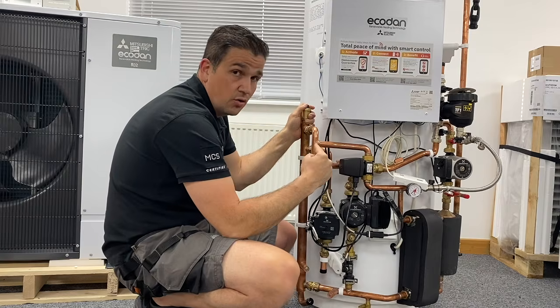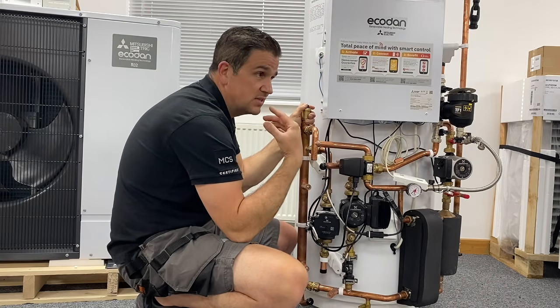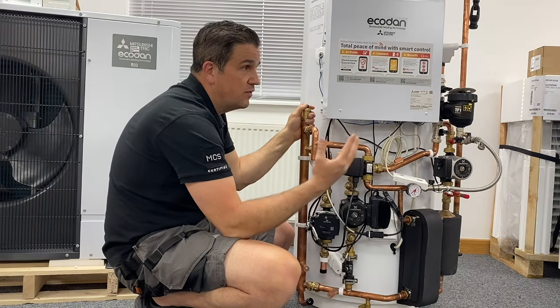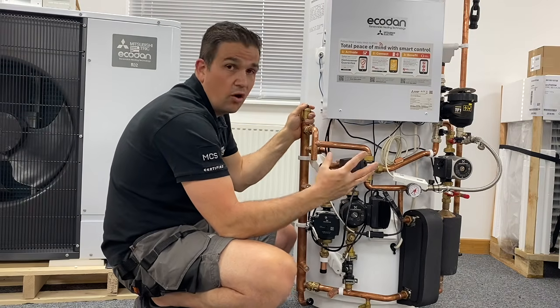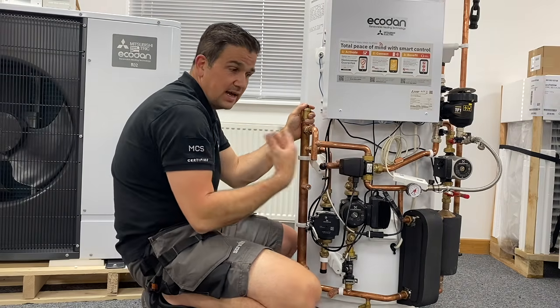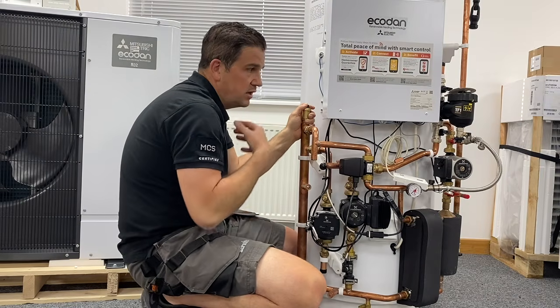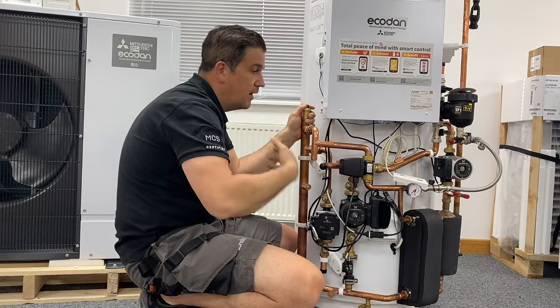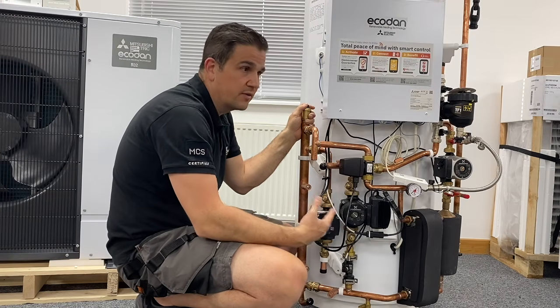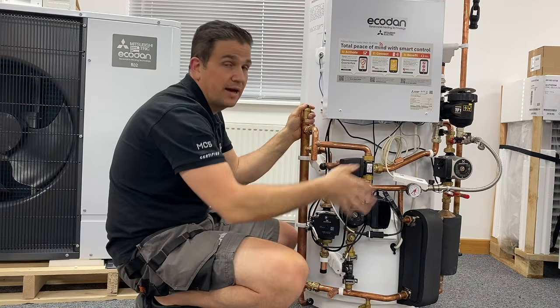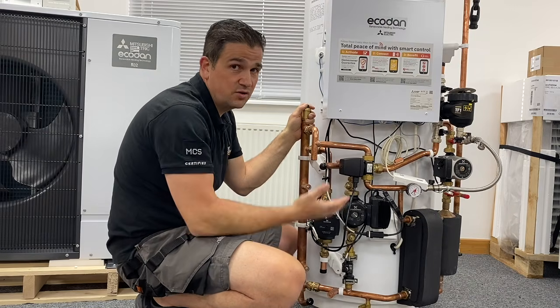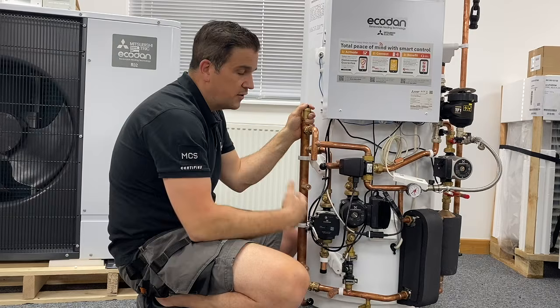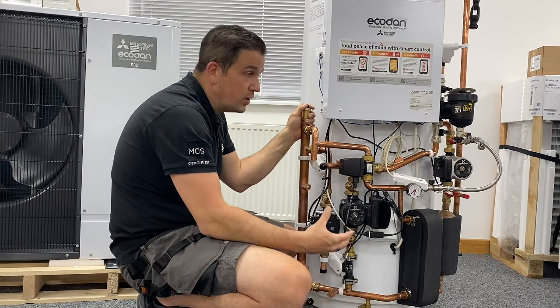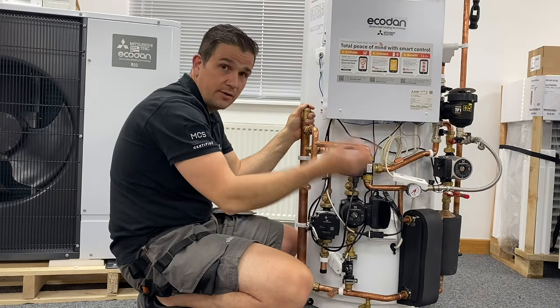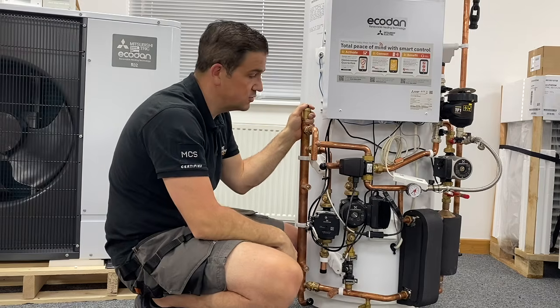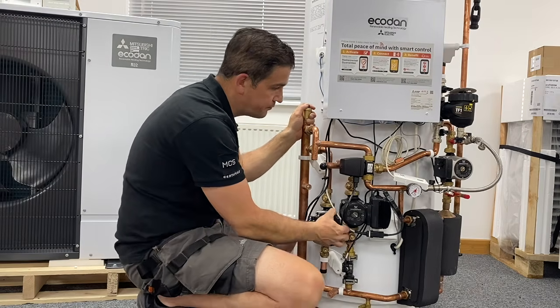So it will prioritise your hot water, and once it's satisfied, or if it's very cold outside and you want to maintain a temperature indoors, you can set these parameters up. You could say, I want you to generate hot water for an hour, then come off for half an hour, keep doing the heating, come back on again until we get to the temperature that we've set on our control. So it's very clever in the way it does that. Or we can just say, give us all the hot water first, then go into heating mode. But that's, again, down to the installer to set these parameters up.